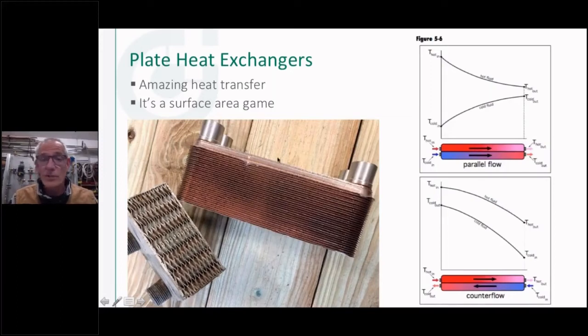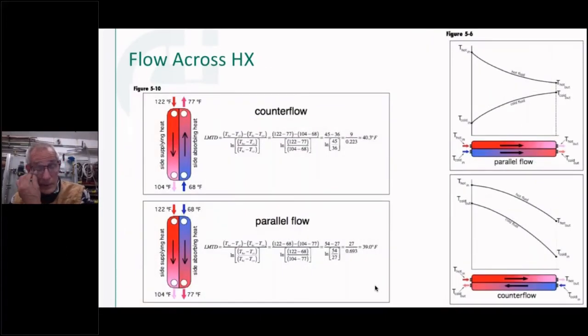If you put one of these in, there's a couple ways you can pipe them. You could go supply and return on both the A and B side, called a parallel flow. You're going to get a little bit better heat transfer if you do a counterflow, because again, you're using that delta T, the cold against the warm. You're getting a better exchange there, and that's basically what these graphs are showing, the difference between the parallel and the counterflow in a flat plate heat exchanger. In fact, this is probably a better example of that.